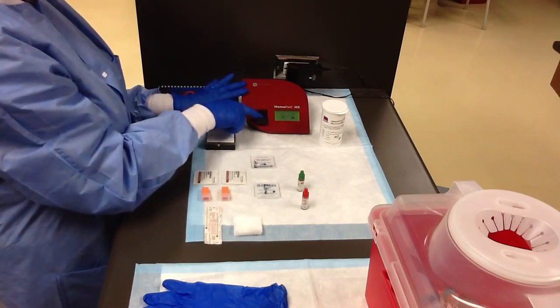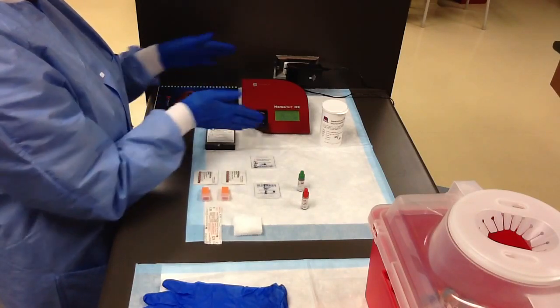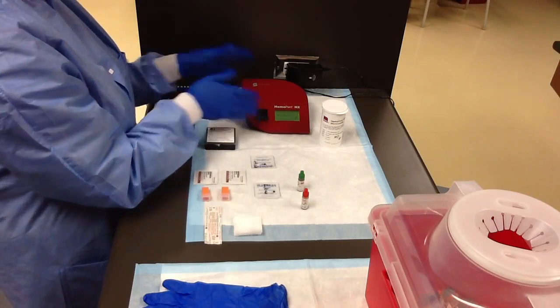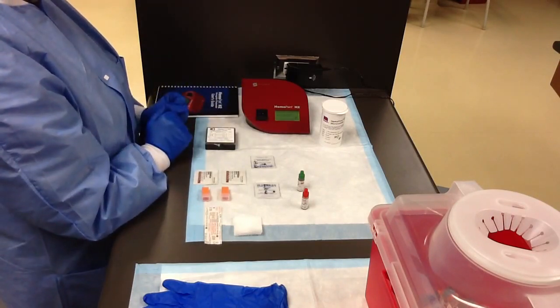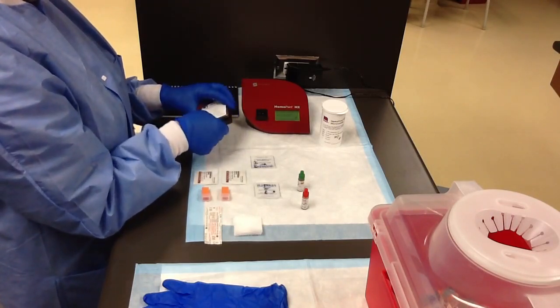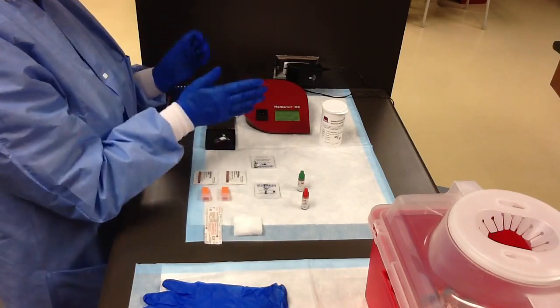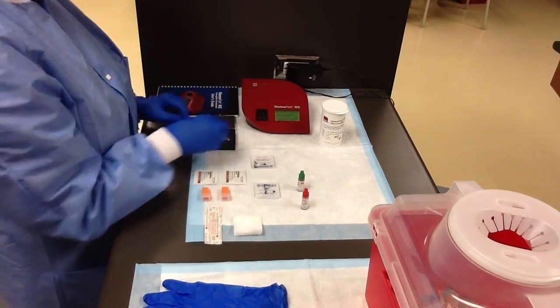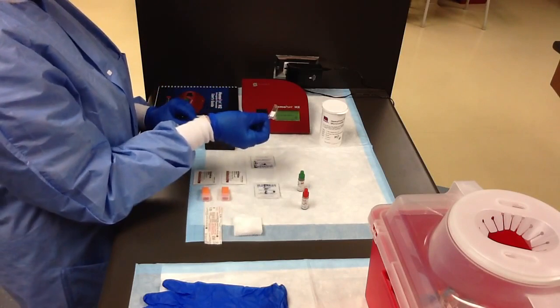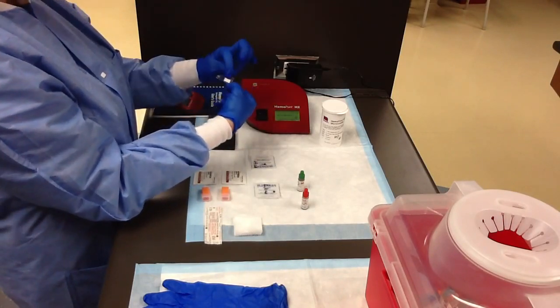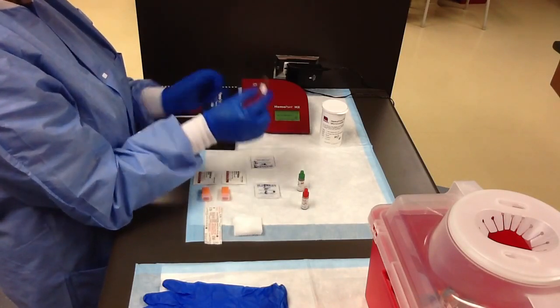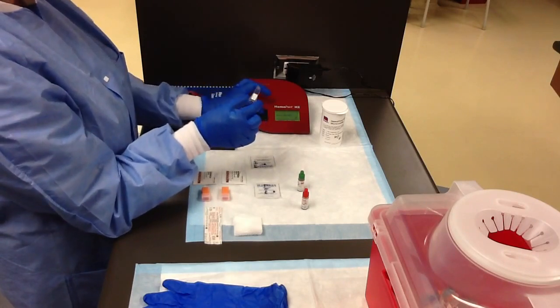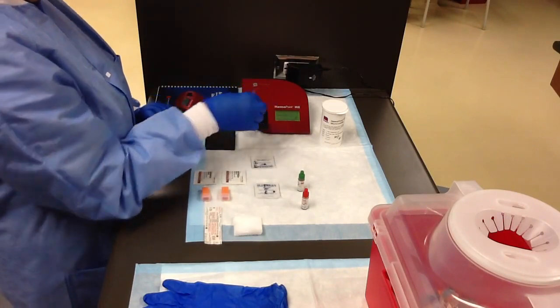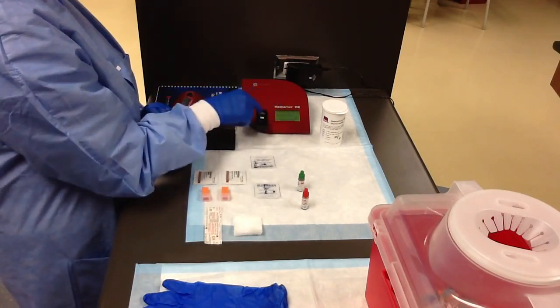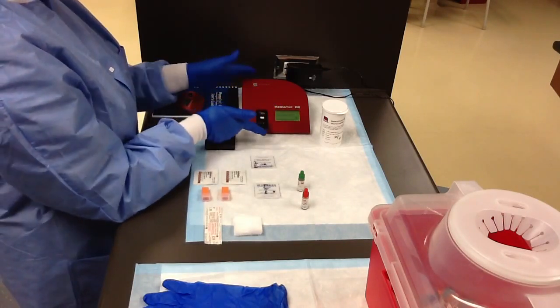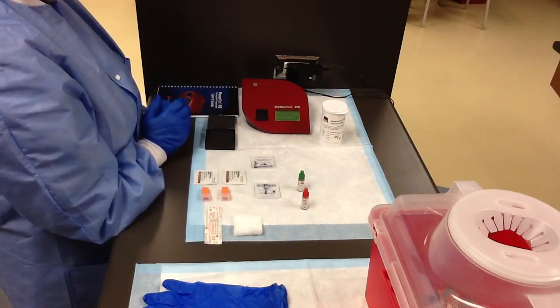You start the process by opening and closing the cuvette holder. That starts the machine into the wake mode. You will take this control cuvette. Note that this is the top part. It must be inserted correctly into the machine. Open the holder manually, place this test calibration cuvette in there, and then close it manually.